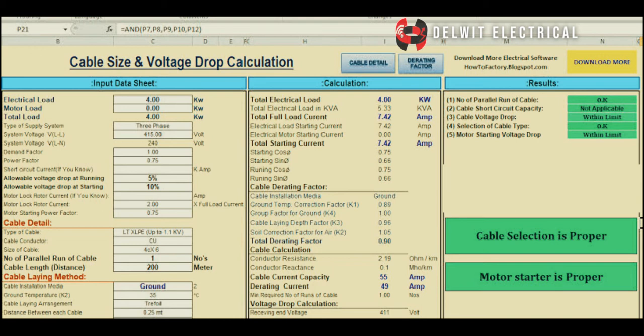This would have been done when the electrical design is being carried out. But unfortunately, when some electricians get to site, they ignore the cable sizing of the electrical design. However, most people do not even bother having an electrical design, so cable sizings are not reflected. They tend to believe the guesswork of the electrician. So it's advisable that if you have an electrical design, follow strictly the sizing that was presented in the electrical design. Don't say because you have been doing it for the past 20-30 years, you now use a 1.5 mm cable for a 5 horsepower AC. That is not done, that will lead to an electrical fire outbreak. So please kindly have an electrical design for your building and stick strictly to the cable sizing for all connections within your household.